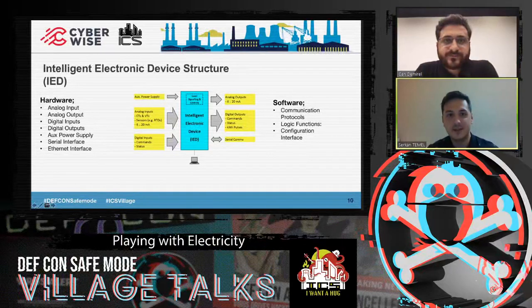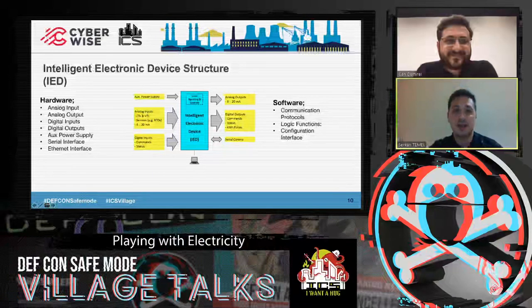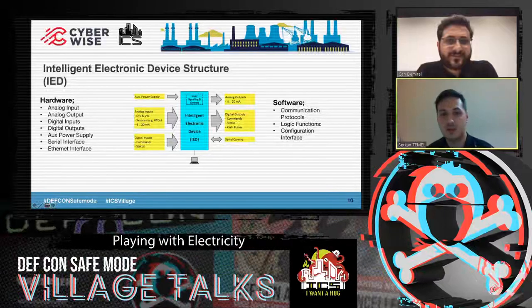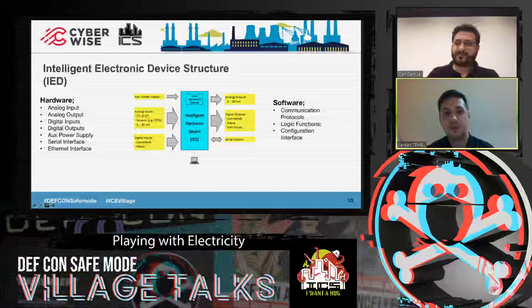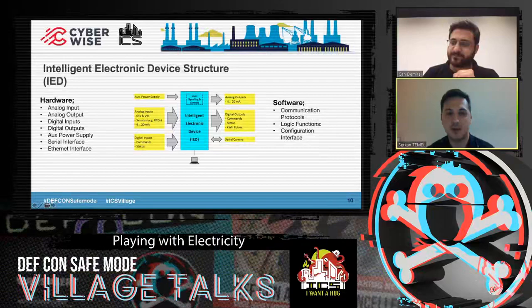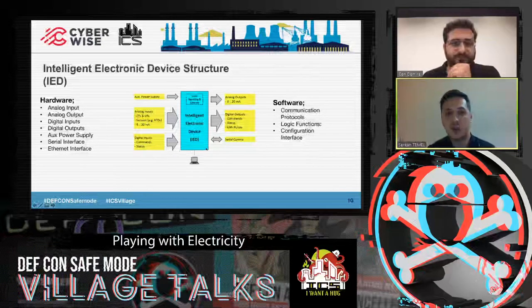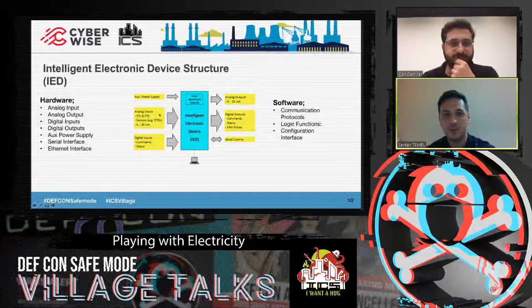Yes, we had the IED device, the protection line device. I would like to say it again, because it is very critical. A protection device has two parts. One is the hardware, the other is the software. On the hardware side, they have analog inputs, analog outputs, digital inputs, digital outputs, and the other is the serial and Ethernet interface. Voltage and current information is taken with analog input modules, and to control analog system values like set points for power, frequency, or voltage, you have to send analog outputs.